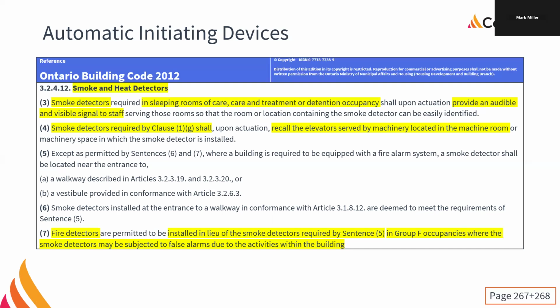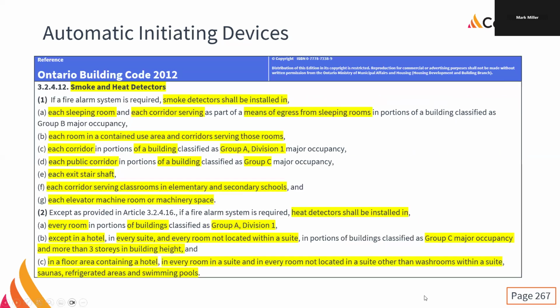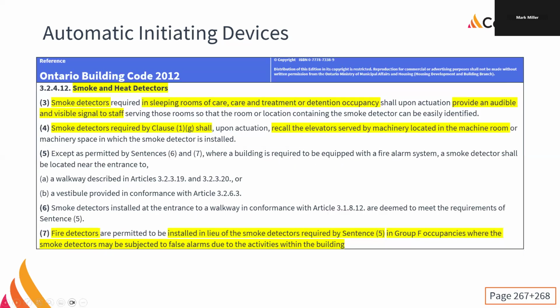The smoke detectors required by Clause 1G, which is 1G, elevator machine room, or machinery space. If we have a smoke detector activate in the elevator machine room, we definitely want to stop using that elevator. That's definitely not a safe thing to be doing.